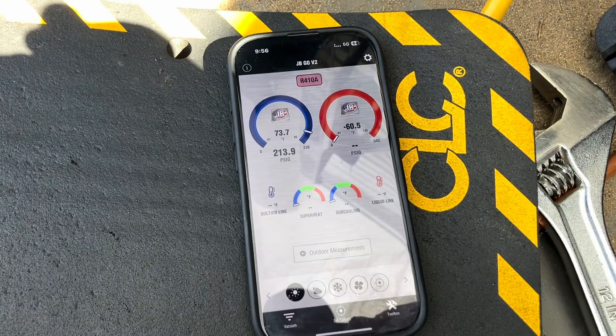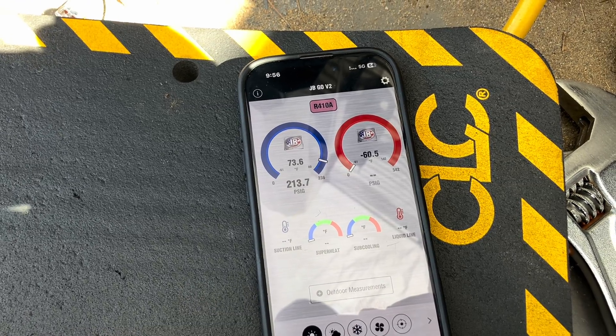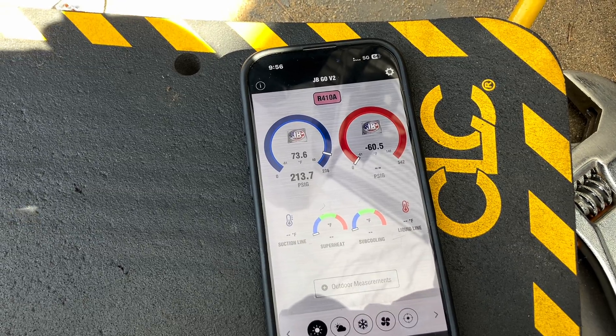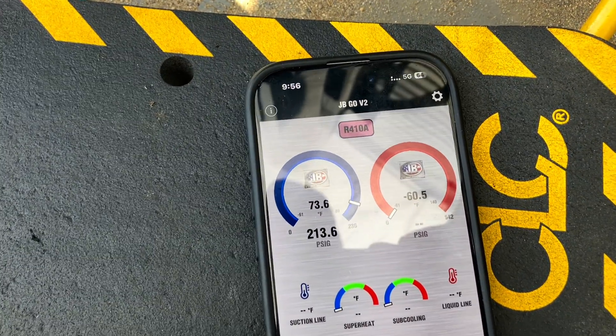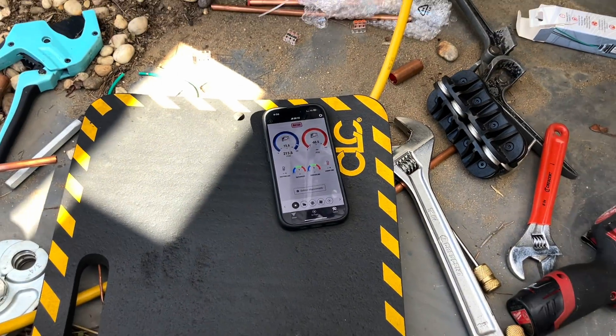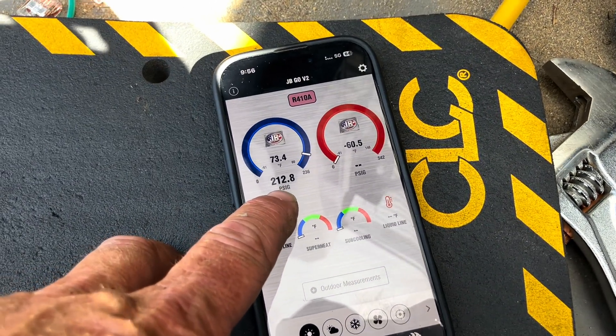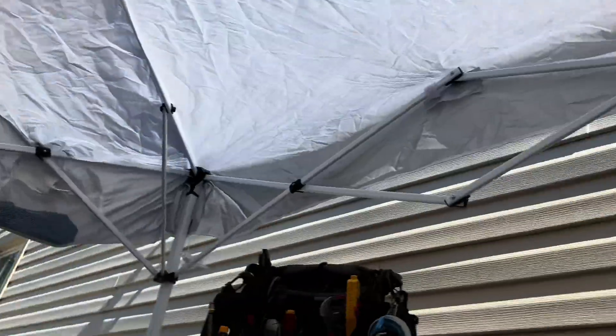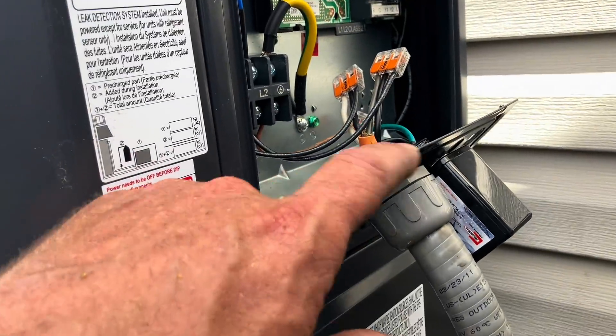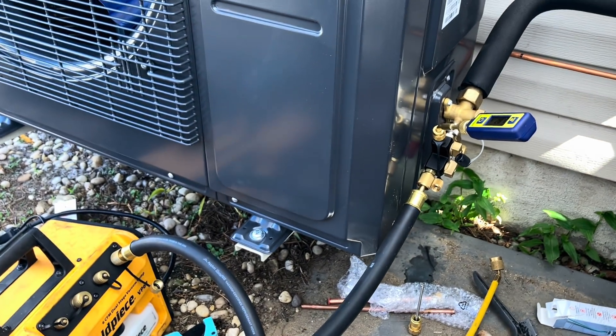Let's fill her up with some nitrogen. We're going to end up being at around 213.8 PSI — let that balance itself out. It is almost four minutes to 10, reading 213.6. All right, hopefully we're good. I took the nitrogen hose off — 212.8. It's 87 degrees here. I'm in the shade. While I'm wiring in my pigtail with the surge protector line voltage, I'm vacuuming down. It held for about 20 minutes without moving.